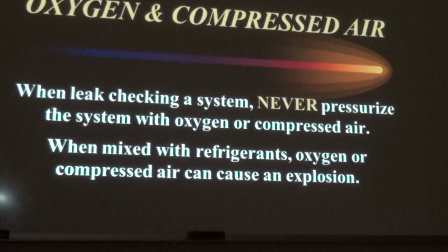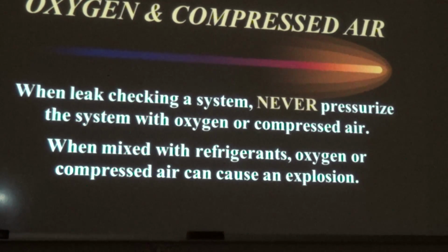Oxygen and compressed air. You can't get by and use pressurized air to leak check a system. You have to use dry nitrogen. When leak checking a system, never pressurize the system with oxygen or compressed air. When you do this, it may cause an explosion when they mix with the refrigerant and the oil under those conditions.